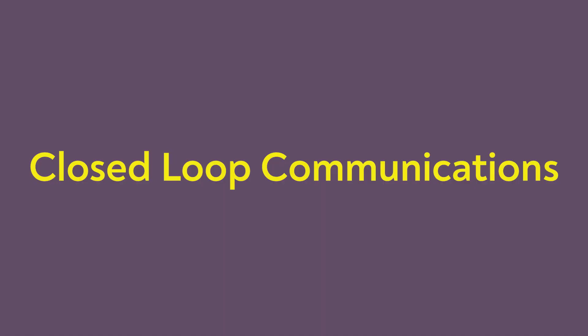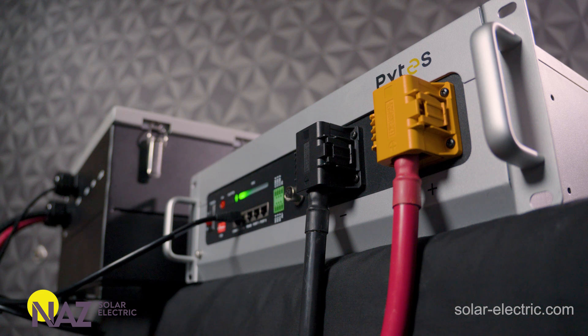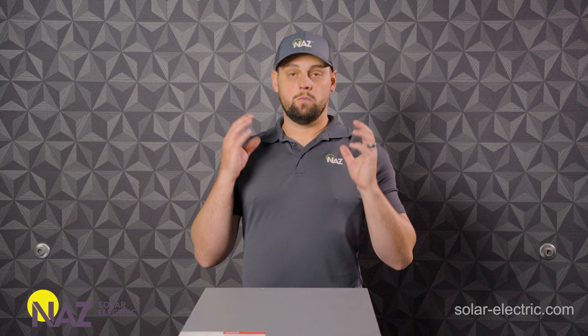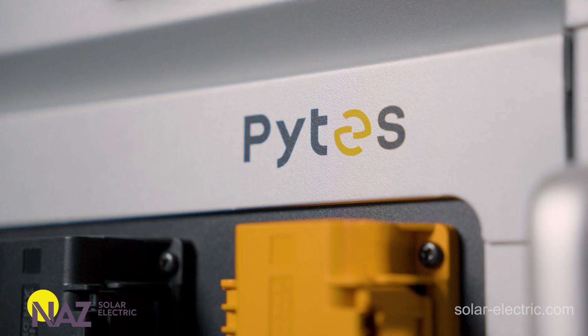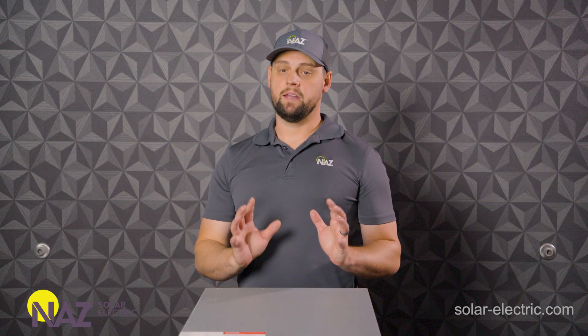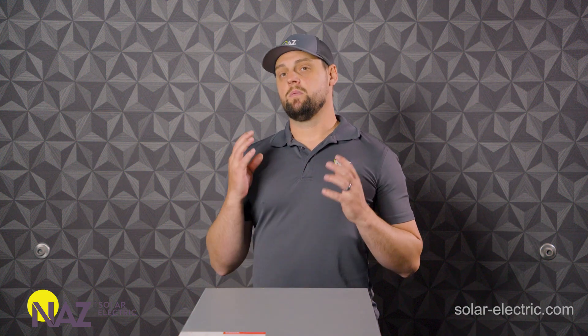For example, Sol-Ark. When we're designing with lithium batteries, it is incredibly important that our systems have closed loop communications. This allows the entire system — the inverter system, the batteries — to understand what is going on. Without closed loop communications, the inverter system is kind of clueless with respect to the batteries and the batteries aren't able to communicate what they need. Closed loop fixes this, and Pytes has this locked down. These batteries can communicate with all sorts of popular products on the market, including Sol-Ark and Victron.